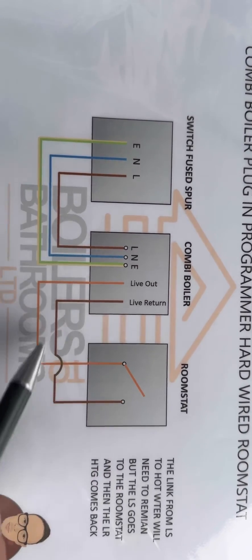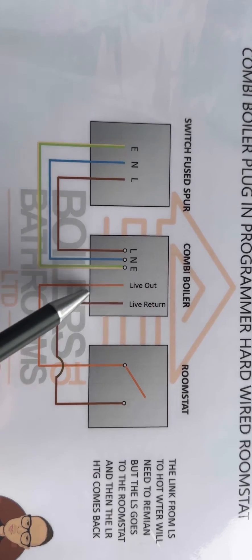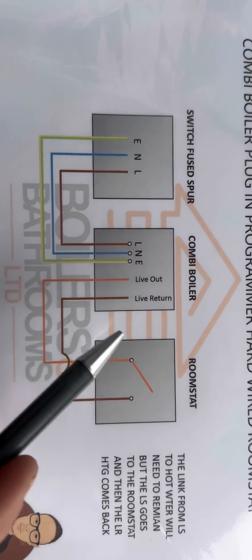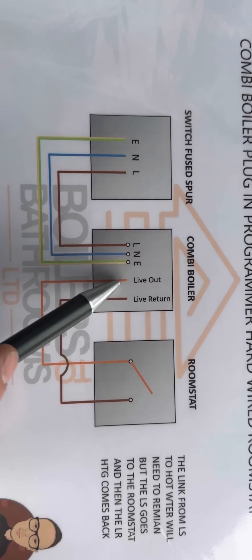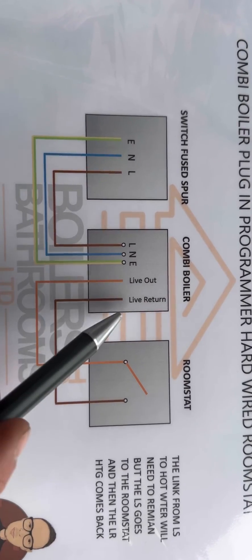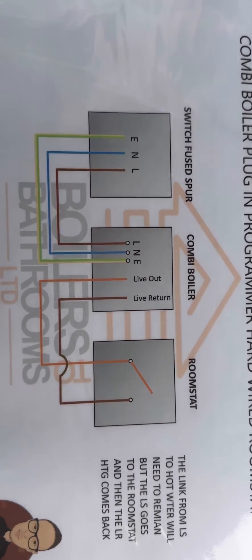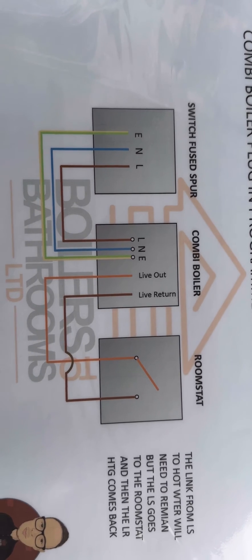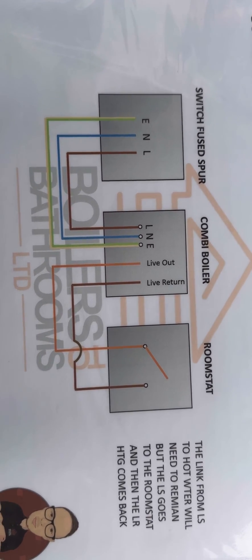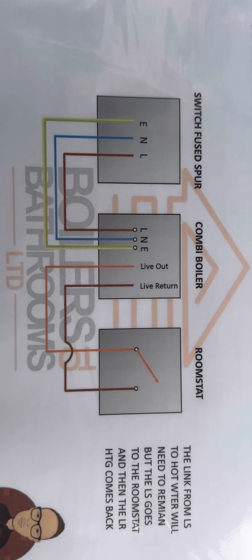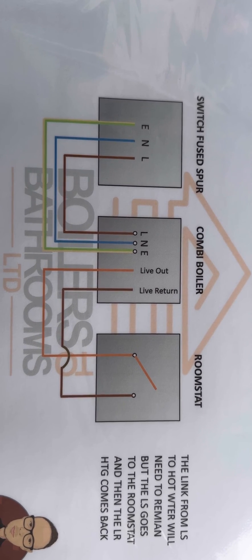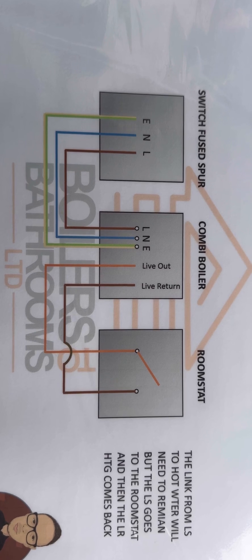Because we were getting the complete loop at 240, we then knew that the programmer was at fault. The voltage was coming back, but the plug-in programmer has the ultimate say, so although it was getting the feedback to fire it just didn't want to fire. As soon as I whipped the plug-in programmer out, the boiler then began to fire.